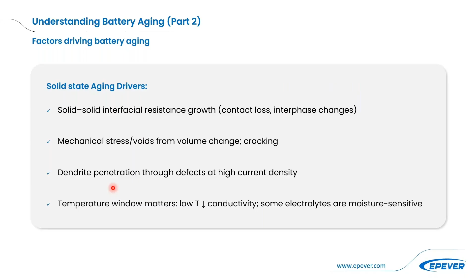In short, we need to manage the state of charge. Comfort is important, but more depth of discharge means a lower life cycle. We need to control temperature, and choose the settings that suit the chemistry we are applying. The aging mechanism is different for lead acid, for lithium, for solid state, so charging settings must be carefully set up for that specific type of battery. That's where the BMS, the battery management system, and good commissioning are critical for higher life cycles.